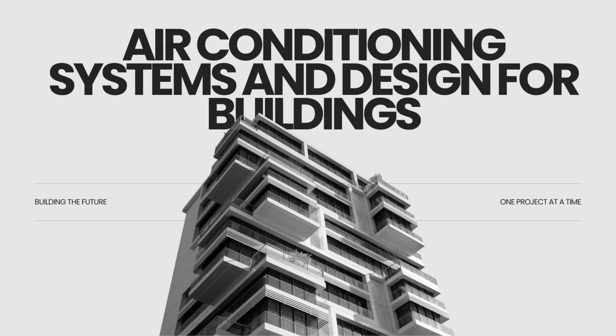Second, the bottom portion of the unit should ideally be installed between 0.75 meters and 1.50 meters above the finished floor level. That specific height range. Why? It's crucial for achieving excellent circulation of conditioned air throughout the room. Cold air is denser and naturally sinks. If it's installed too high, the cold air might just fall straight down, leaving the upper parts of the room warm. If it's too low, it might not mix well with the warmer air higher up, creating cold spots near the floor. That height range, roughly 2.5 to 5 feet, promotes optimal mixing of the cool air with the room air. Okay, height matters for circulation.